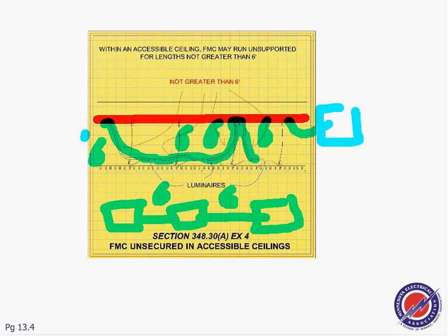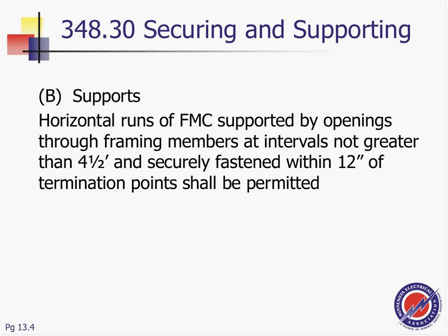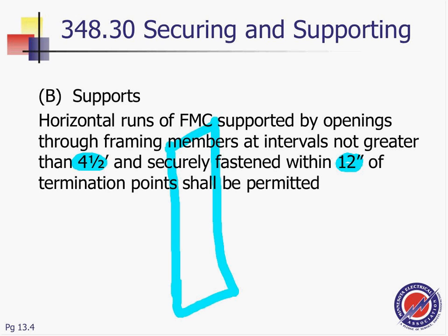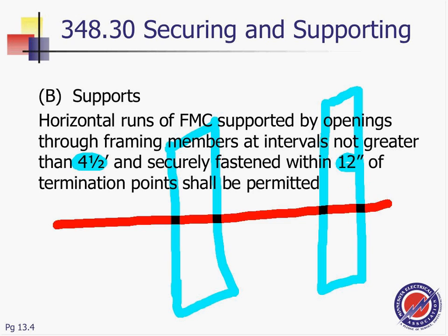Okay, basically we got that one. Supports, as I said, when you support, here's your supporting means. It shall be horizontal supports by openings. Now, if you're pulling it in studs, like they used to do, I believe in the 70s, I know houses wired with flex. If studs, guys, if you can maintain, and just imagine from this hole to this hole is 4.5 feet, and I know there are more studs than what I showed. I'm just showing 2 studs, 4.5 feet, guys. They don't need to support it.